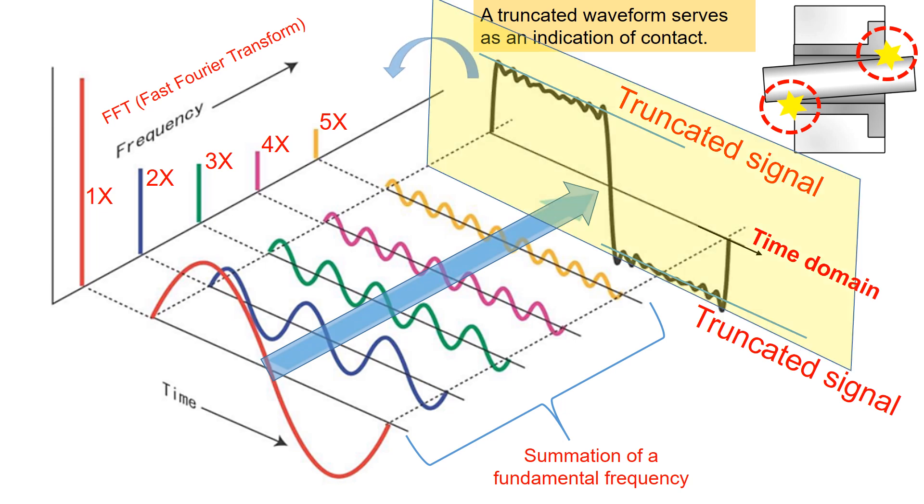By using FFT, the truncated signals in the time domain are translated as harmonic frequencies in the frequency domain. The truncated waveform is represented by harmonics such as 1x, 2x, 3x, 4x, and so on.